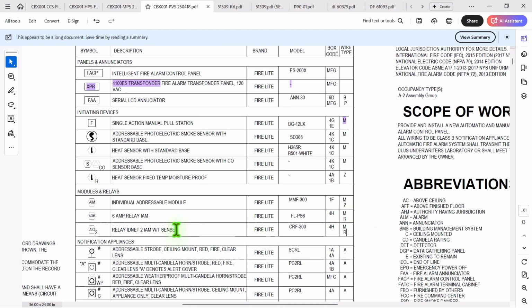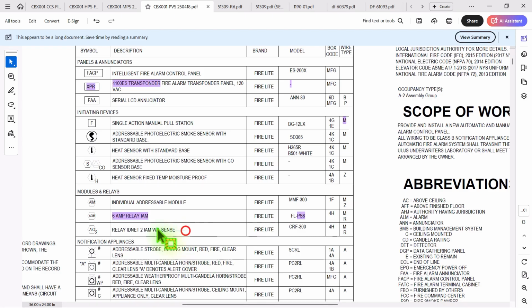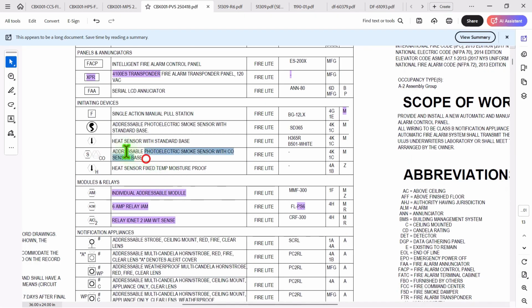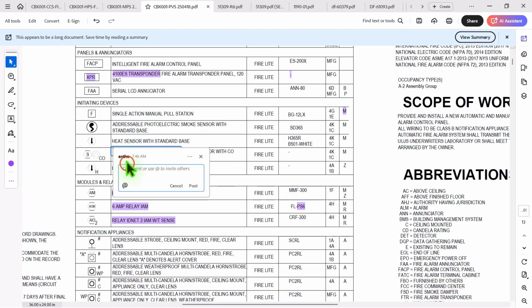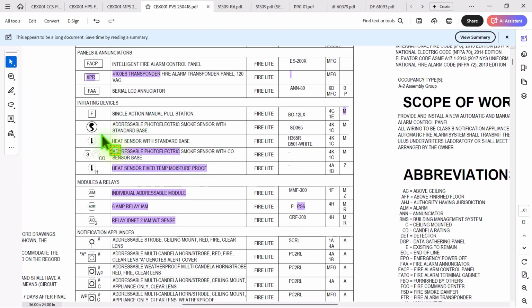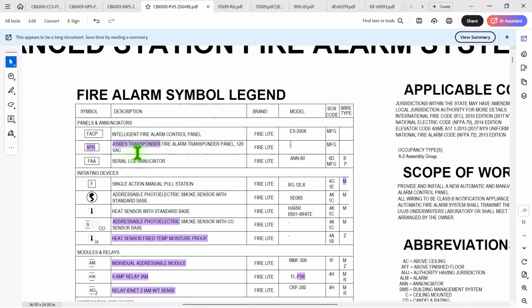Then when you get down to the relay, you're going to change this to addressable control relay, and the model is CRF300. Remove this, change this to single input module. Remove this - there are no COs, no smoke COs. Also remove this. So we only have fire alarm control panel, a remote annunciator, pull stations, smoke detectors, heat detectors, some modules, and also some output devices.